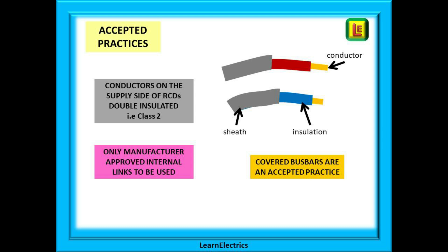Conductors on the supply side of the consumer unit must be double insulated — in other words, making them Class II and giving them two layers of protection. You can see from the picture that the copper conductor is surrounded by first a layer of plastic insulation, and then this is encased in a second layer of plastic sheathing. This is exactly the arrangement that we have with meter tails. Also, only manufacturer's approved links should be used inside the consumer unit, as the manufacturer has designed the internal links to satisfy the safety requirements for their consumer unit. Copper bus bars supplied by the manufacturer and protected by a plastic guard are also acceptable, and using a torque wrench to secure screws to the manufacturer's recommendations is also a requirement.